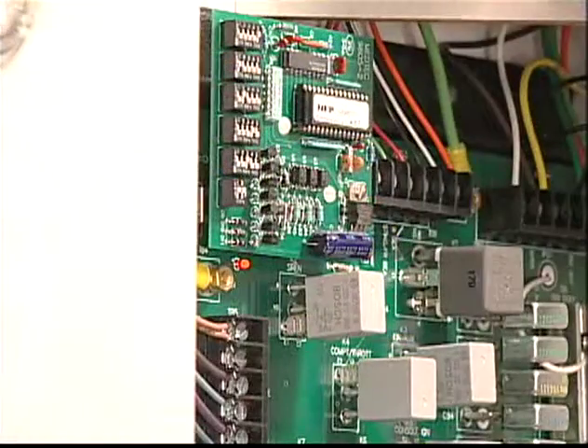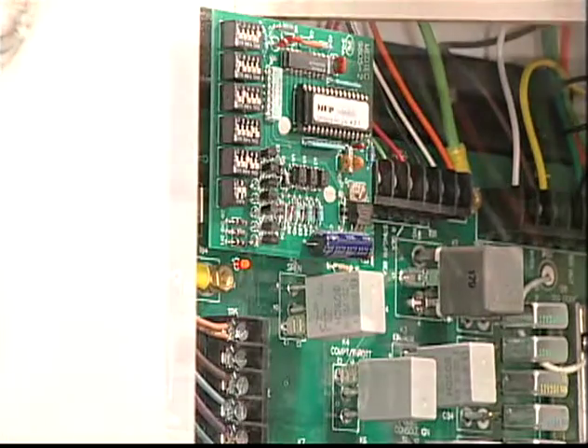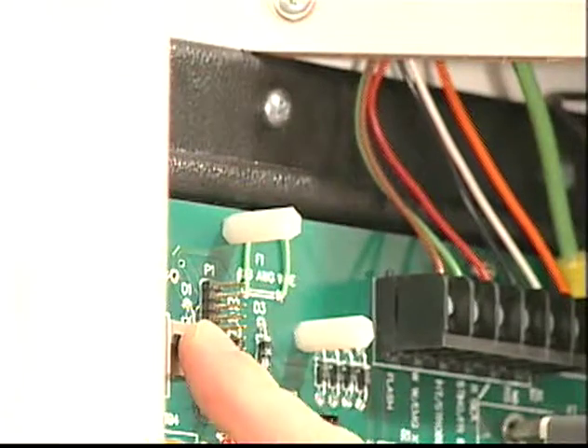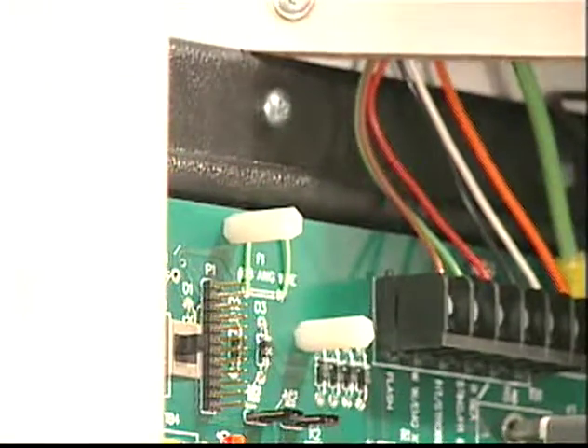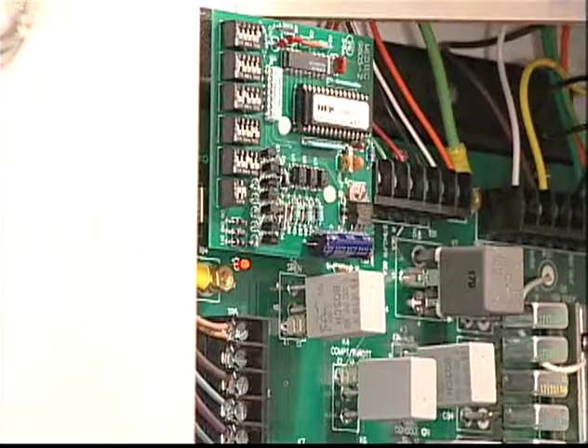If the load manager sequencer fails to operate, remove the load manager sequencer PC board. Push the manual bypass switch up to allow emergency operation of loads that are controlled by the load manager sequencer. Medtec has developed and installed this device in your ambulance to increase the efficiency of the chassis electrical system.